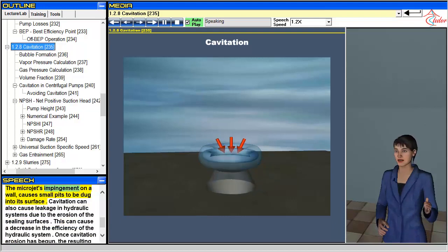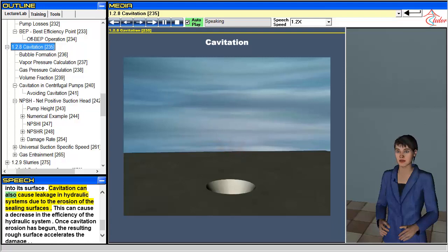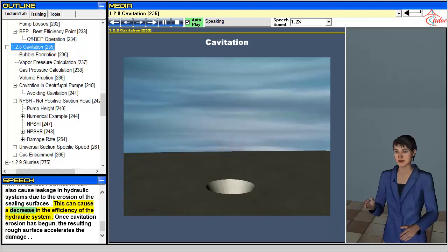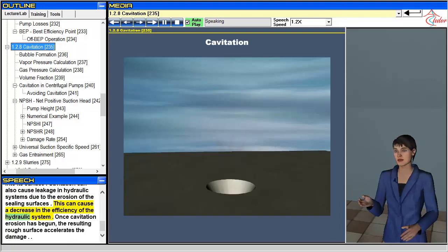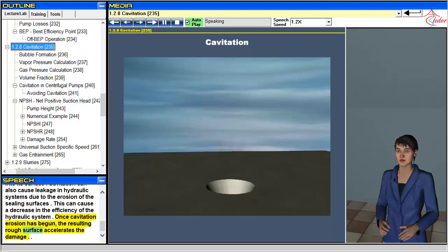The microjet's impingement on a wall causes small pits to be dug into its surface. Cavitation can also cause leakage in hydraulic systems due to the erosion of the sealing surfaces, causing a decrease in the efficiency of the hydraulic system. Once cavitation erosion has begun, the resulting rough surface accelerates the damage.